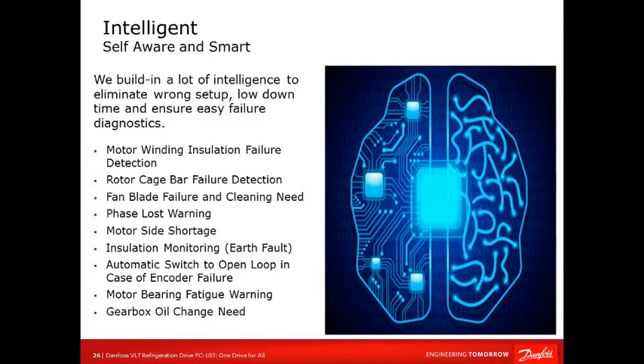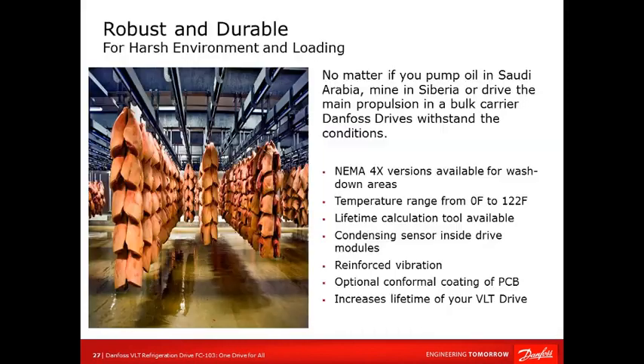And again, getting back to the intelligence, the expectations are, you know, the drive actually has more capability in it. Some of those things, for example, here we're showing motor winding insulation detection failure. Basically the controls of the drive can, if it's sensing an issue like, for example, earth fault, you can program the drive to, if this happens, then bypass or do this or send an alarm. There's a lot of flexibility. And again, Danfoss can have a lot of control built into the drive, or Danfoss could be receiving input from a controller telling the drive what to do. So we have a lot of built-in smarts built into the drive for robust durability.